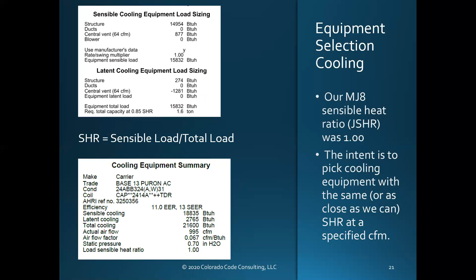So the idea is to get a piece of equipment as close as we can to the same sensible heat ratio. The plan is to pick the cooling equipment with the same or as close as possible sensible heat ratio at the specified CFM, and we'll look at that table in a second.